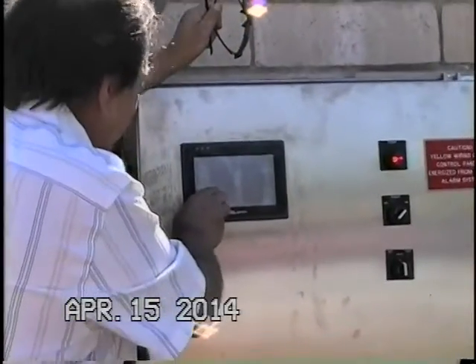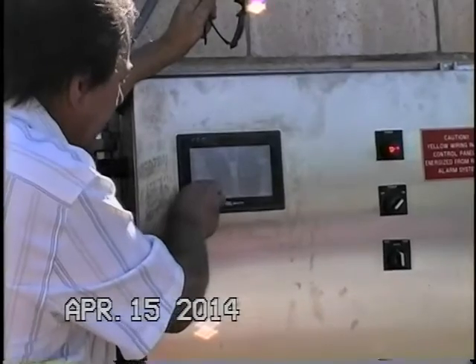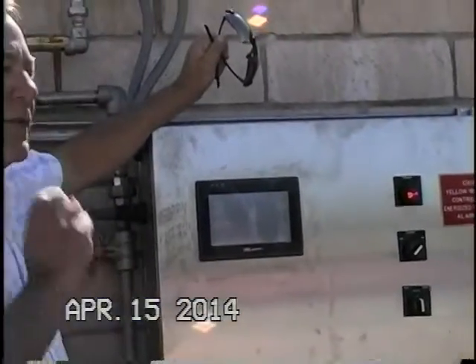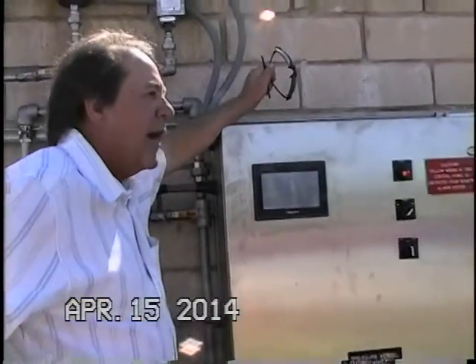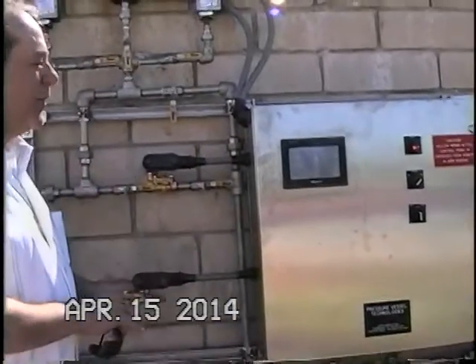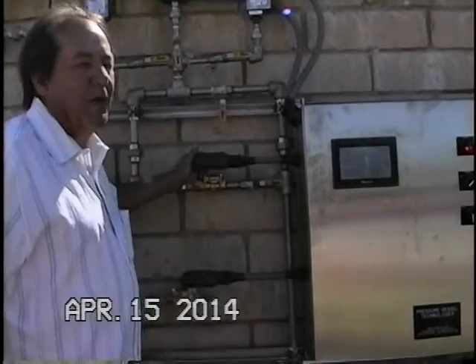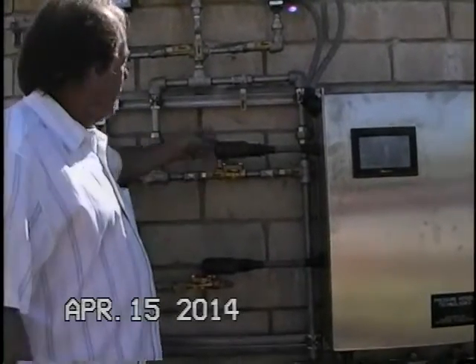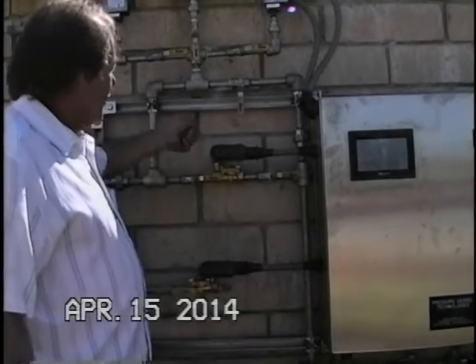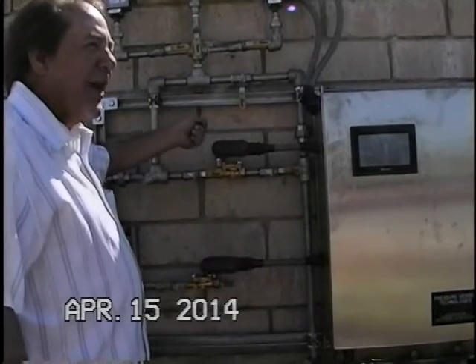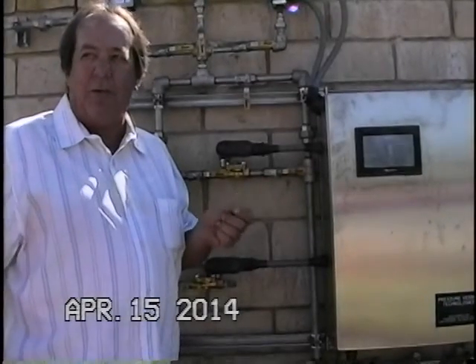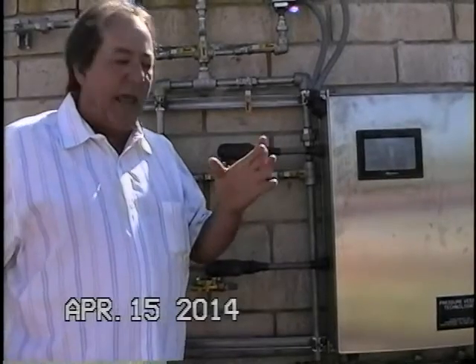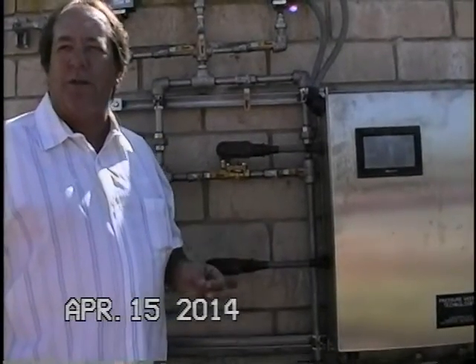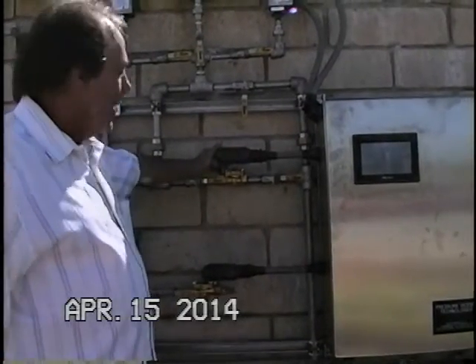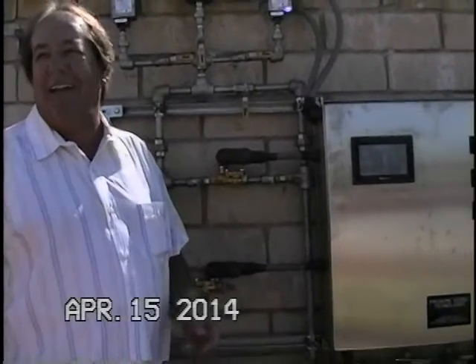Anytime there's an actuation or we're adding air, you will be able to see it go to green, and then it will also say on. So you can know whether or not we're actually sending power out to the solenoid valves. The other trick on the solenoid valves: sometimes you can't really tell whether or not they're on or off. I always use a little screwdriver because we're creating a magnetic field on the coil. You can put a screwdriver right on top of the solenoid valve and you'll feel that little vibration. If you feel that vibration, then you know that coil is activated. That's just a nice little thing to know that you're getting power to the solenoid valve. Obviously on the vent valve, if it's venting air, it's actuated.